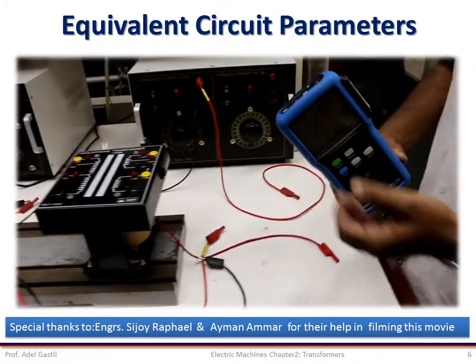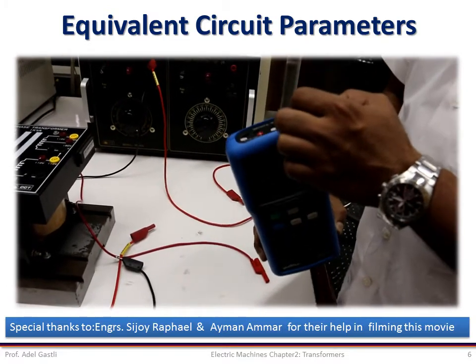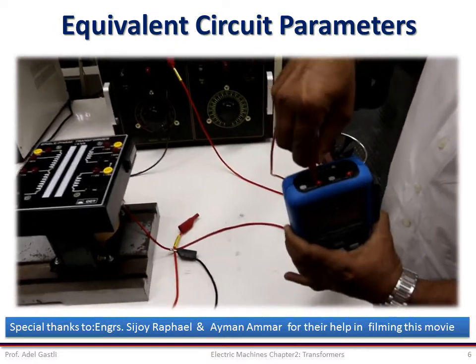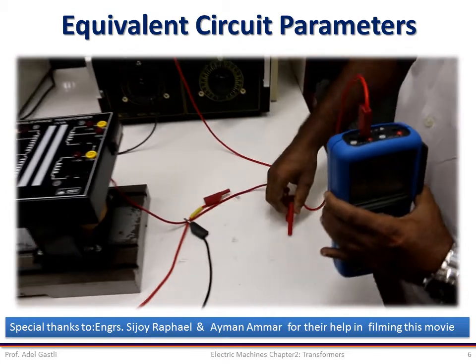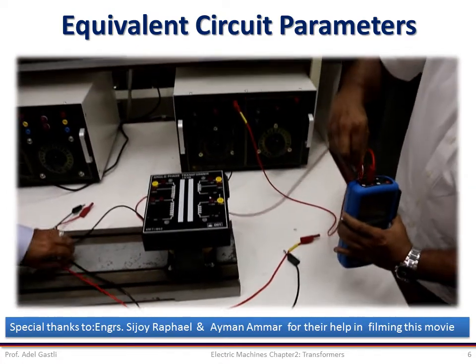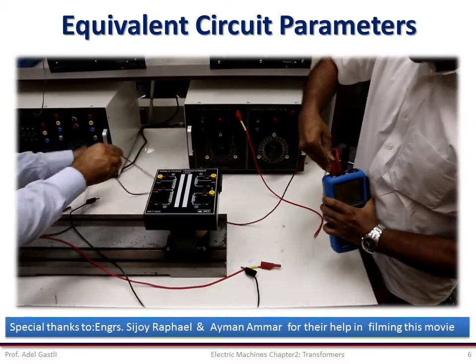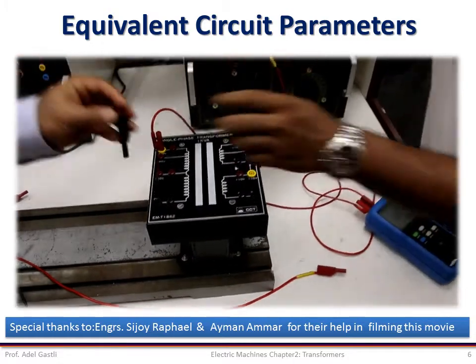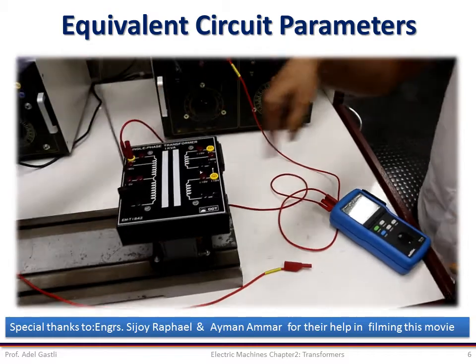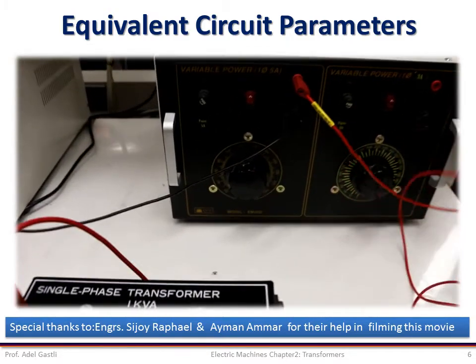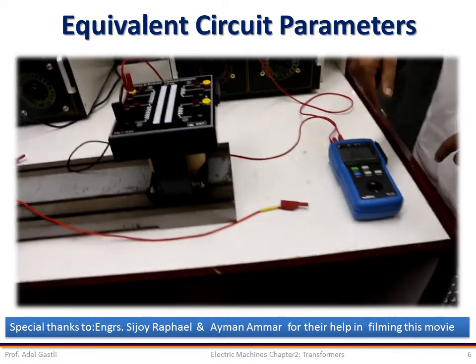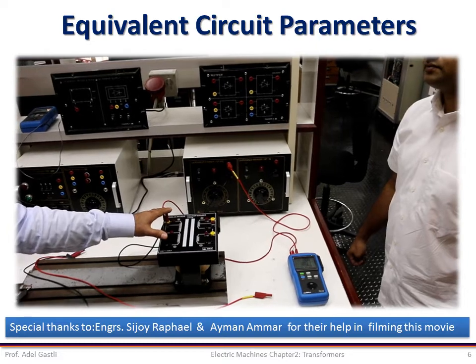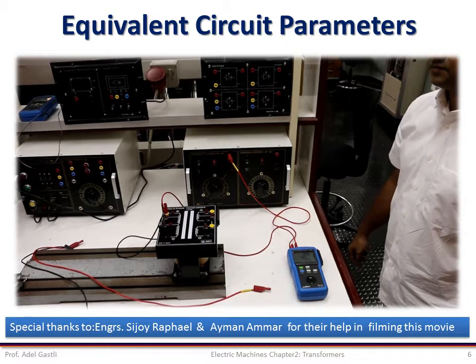This device has a current coil as well as a voltage coil. We first connect the power supply to the current coil: the line should be connected to the plus, and from the negative it should go to the positive terminal of the transformer. From the negative of the coil, it should go back to the neutral of the power supply. So the ammeter is now connected. We are applying the source voltage to the primary winding of the transformer while also measuring the current, which is why the ammeter should always be in series in the circuit.